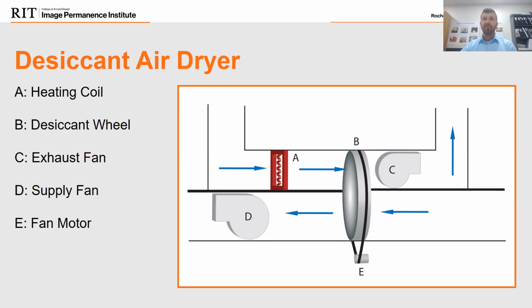And that is the air from the space, the processed air. You're going to be bringing that air in. It's going to cross over the coil, cross over the wheel, if you will. And then the fan's going to exhaust that air into the space after it's crossed the wheel and been dried out. The balance of that air, typically like 60 to 75% of the air, is going to cross this bottom part. The top part of the wheel is going to cross what they call the regeneration side of the air, and that's going to cross over a heating coil, which is going to essentially superheat that air. I believe I've seen some information that says it's about 212-ish degrees for one unit.